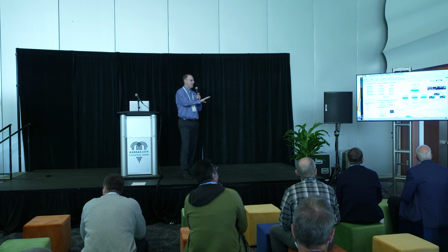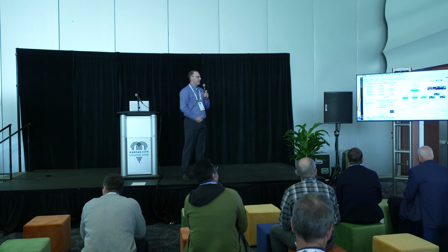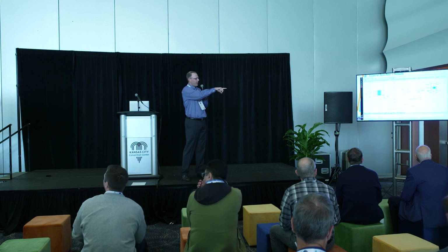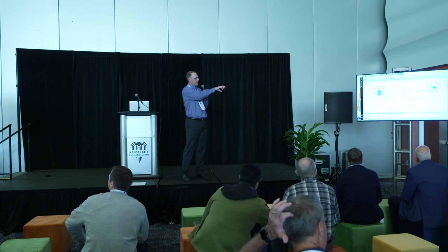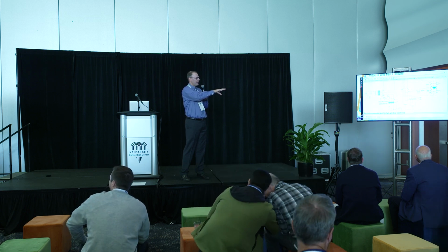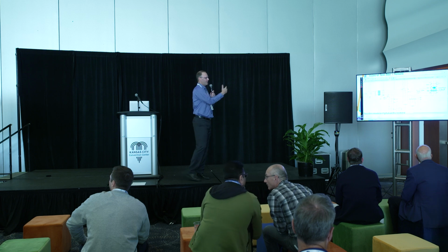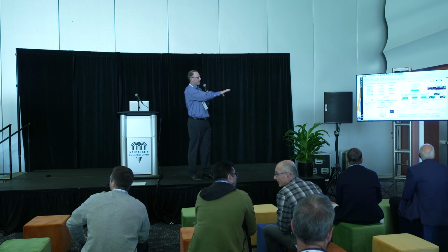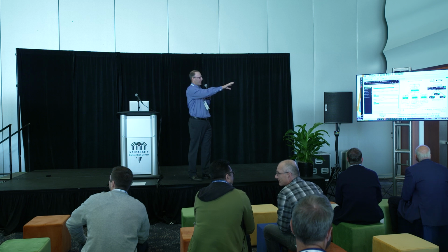So you can see here, this is the front end of the simulator. We have the live measurements of the grid at the top. We also have measurements of the capacitor bank. This is the actual single line diagram of the topology based on the DTE circuit. We imported CYME to build this in the simulator. So you have the battery storage system, the capacitor bank, and the regulator.